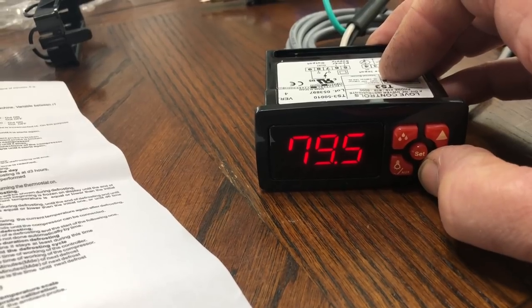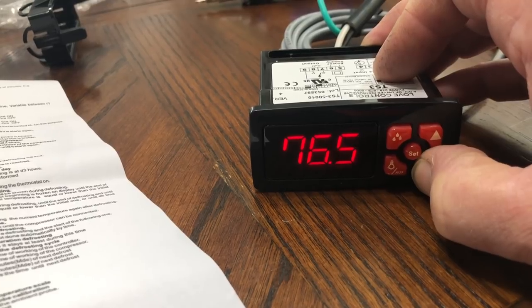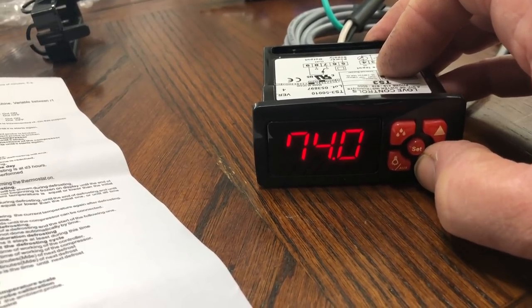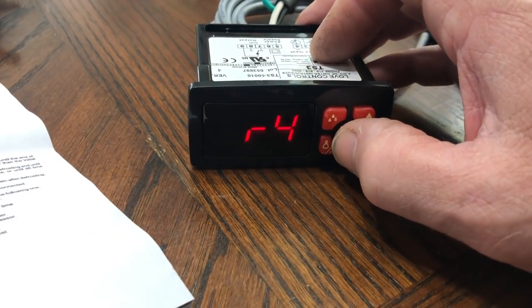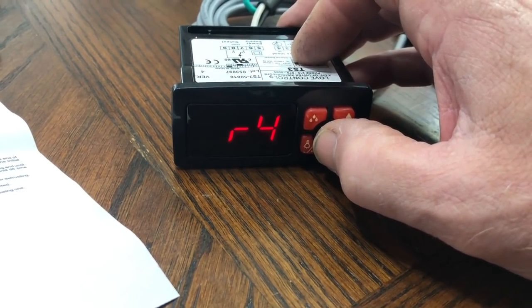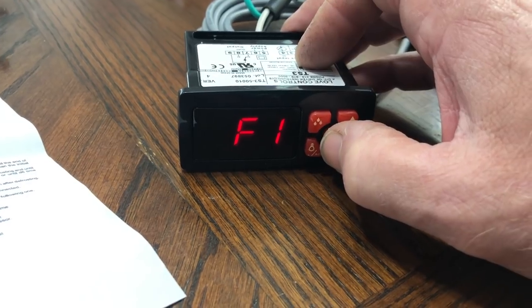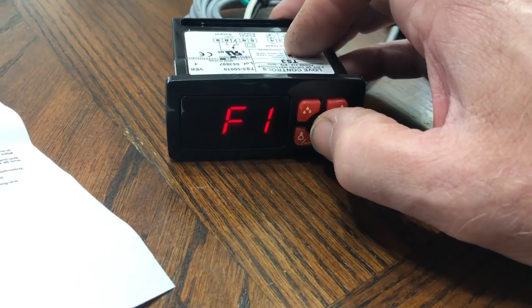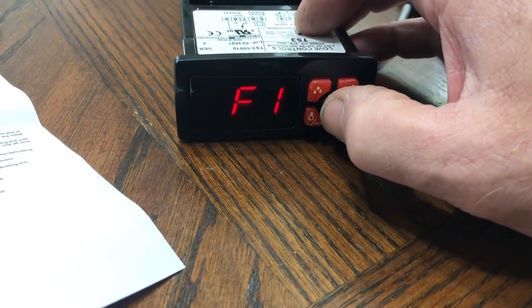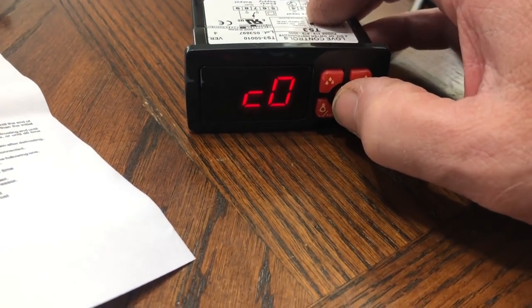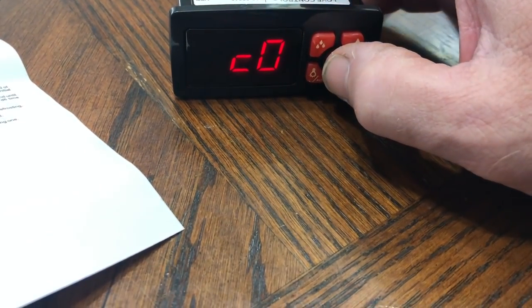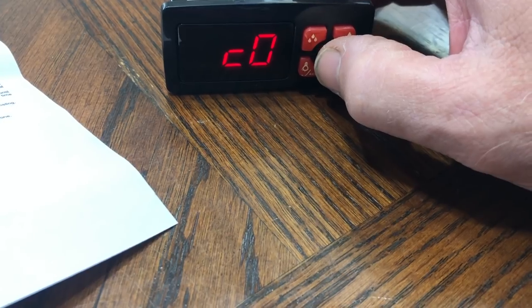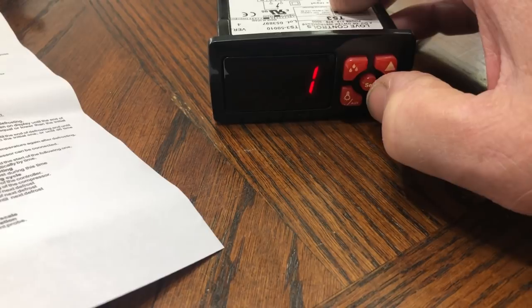You can come down and put like, like what would the maximum you'd want have them be able to, maximum set. You could turn it way down. You get the idea there. R4 is night set point variation. And the factory setting on that is zero. Then you can go up. The next one is F1. Stop the compressor fans with the door open. This one doesn't really have a door sensor. I think that's a generic program from these guys. There is no door sensor on this control. That might be just a generic printing that they have.